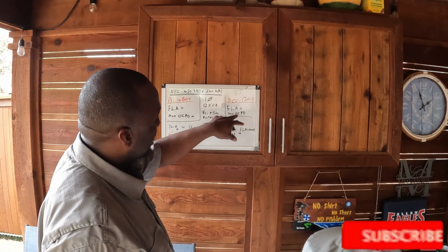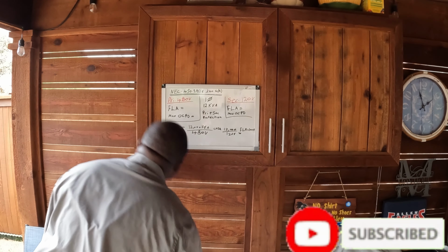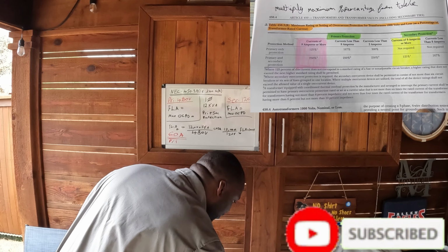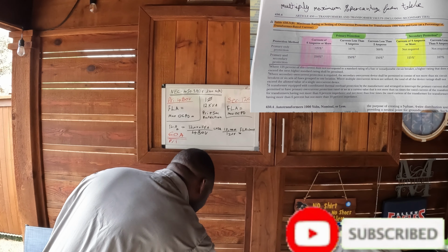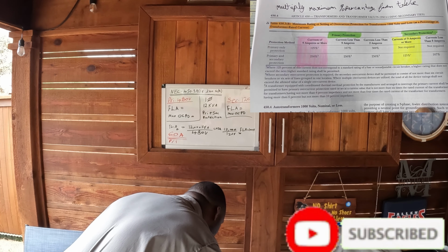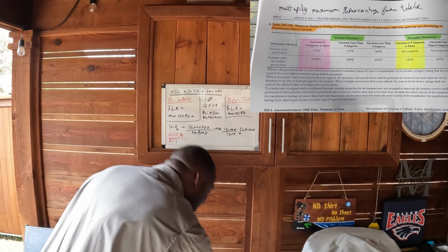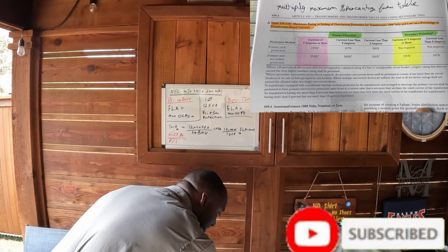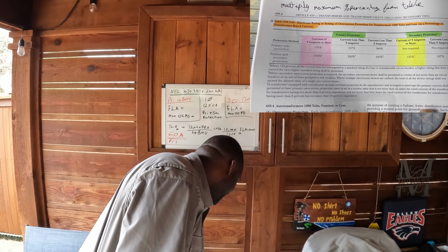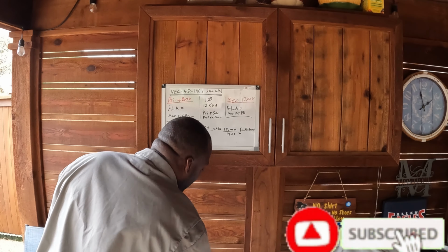Again, we're looking for the maximum overcurrent protective device. So that's gonna take us back to article 450.3(B), right? And then you're gonna look, it's over 9 ampere. You're gonna look in the same table beside the primary and look into the secondary, and you're gonna multiply it by 1.25 because you're doing primary and secondary.